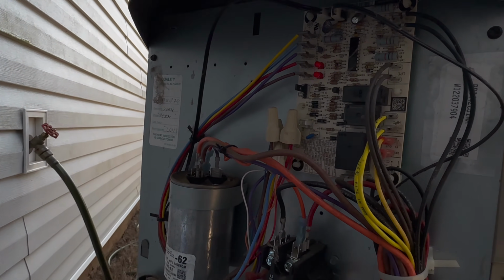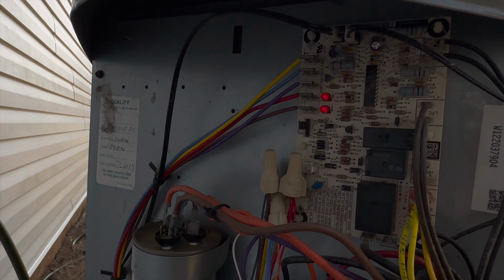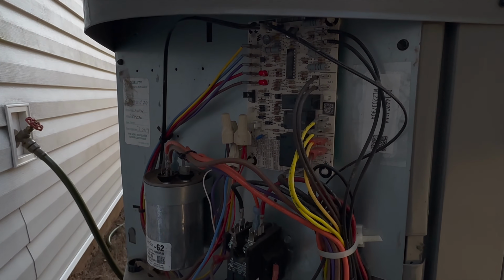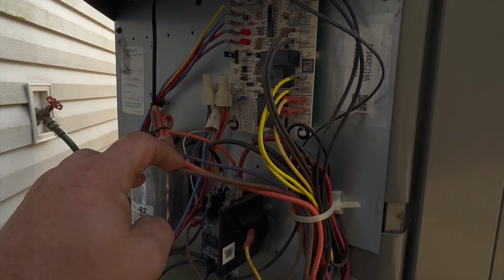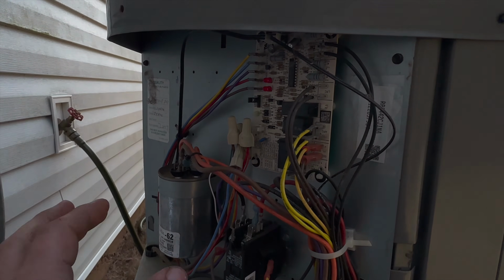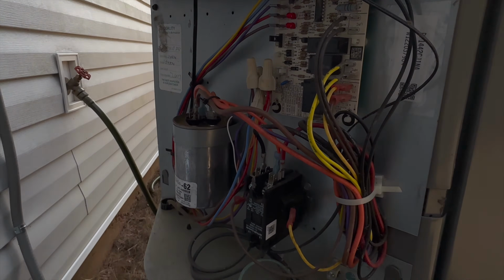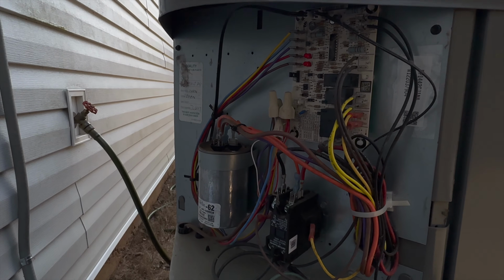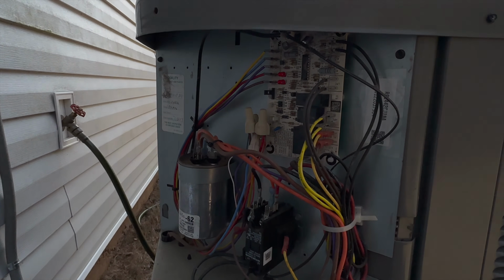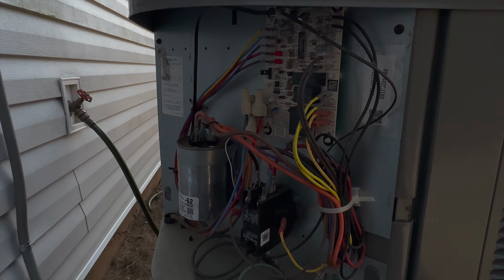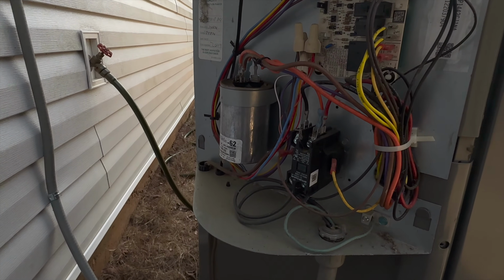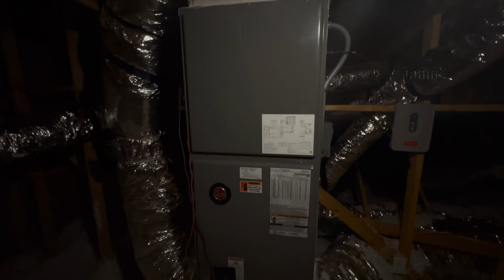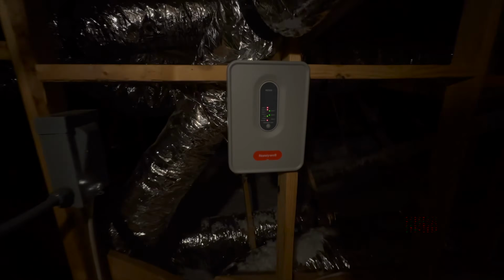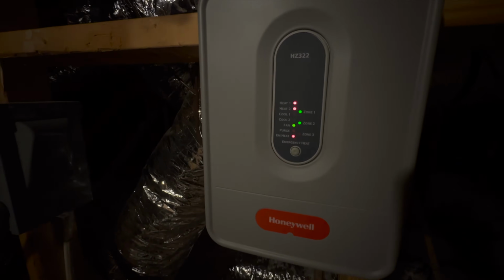Unfortunately, when the power was turned off, it reset any type of fault code that would have been on here. So that's sort of a bummer. You always like to get to the situation with the system locked out so you can see what exactly had happened before. Another heat pump. So if I had to guess, it's going to be something to do with airflow. Lock this thing out more than likely, but that's just speculation, going off of what typically is the case with these heat pumps around here. Both calling for heat. Both zones should be open.